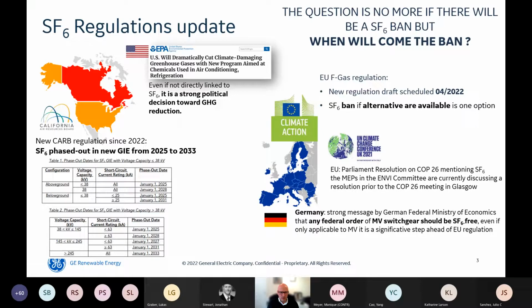If you look at the dates here—maybe small for many of you—one key threshold, which I believe ARPA-E had particularly in mind for this funding opportunity: at 245 kV, less than 63 kiloamps, so basically 40 or 50 kiloamps, starting January 1st, 2027, utilities in California would not be able to buy new gas-insulated equipment anymore—outdoor equipment like a dead tank breaker, or indoor GIS. A GIS can be outdoor too, but they can't buy 245 kV, 40 or 50 kiloamps anymore, moving toward 63 kiloamps. So it's really happening in California.